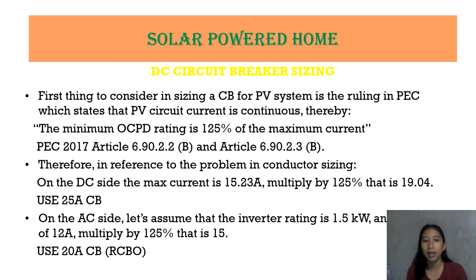So, makikita natin yan sa ating PEC 2017, Article 6.90.2.2 and Article 6.90.2.3. Therefore, in reference to the problem in conductor sizing, on the DC side, the max current is 15.23 ampere multiplied by 125%. So, the answer would be 19.04. So, gagamitin natin yung 25 ampere CB. On the AC side, let's assume that the inverter rating is 1.5 kilowatts. Multiplied by 125%, that is 15. So, ang gagamitin natin dito ay 20 ampere CB RCBO.